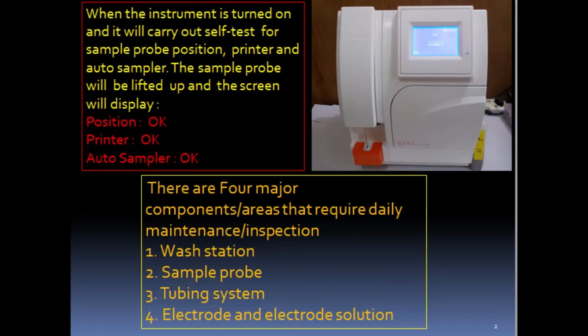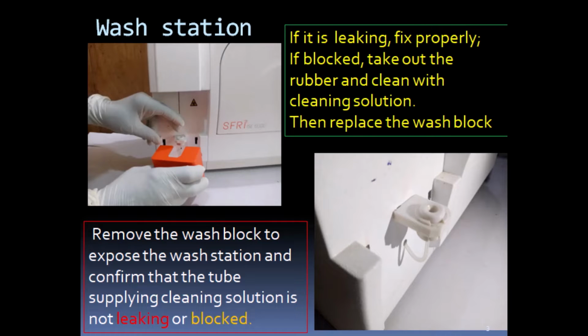For the maintenance, there are four major components or areas that require daily maintenance or inspection, and they are wash station, sample probe, tubing system, electrode, and electrode solution. For the wash station maintenance, remove the wash block to expose the wash station and confirm the tube supplying cleaning solution is not leaking or blocked. If it is leaking, fix properly. If blocked, take out the rubber and clean with the cleaning solution, then replace the wash block.